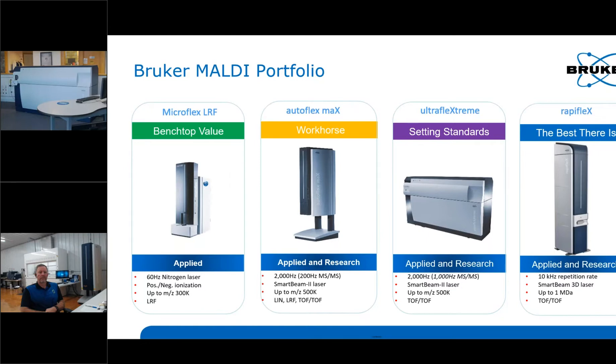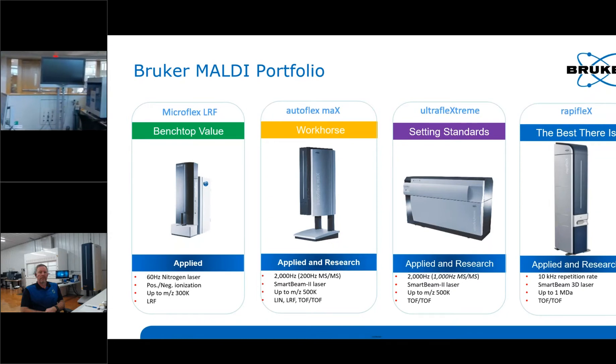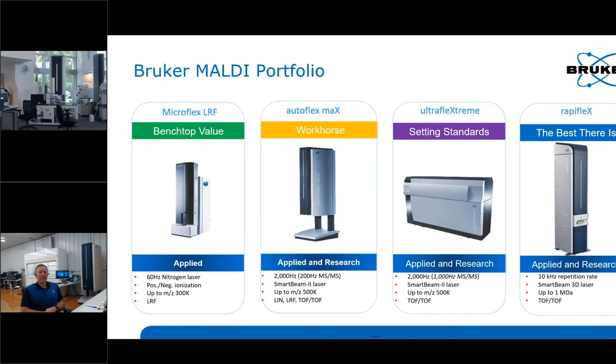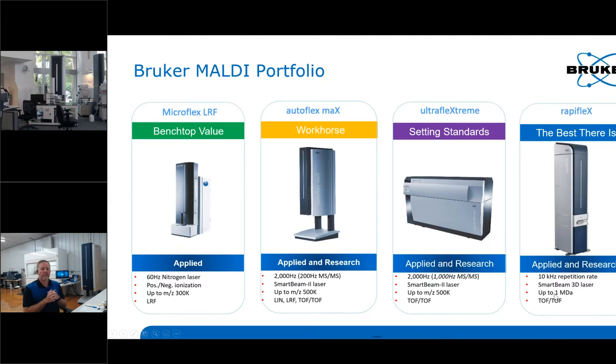At the top of the chain is the Rapiflex, which is the best there is — with higher specs and higher speeds, especially for imaging experiments. It has the fastest laser in any MALDI instrument ever made, capable of up to 10 kHz repetition rates. It's equipped with a SmartBeam 3D laser, an improvement over the SmartBeam 2, with a high mass range up to 1 million Dalton and TOF/TOF capabilities.